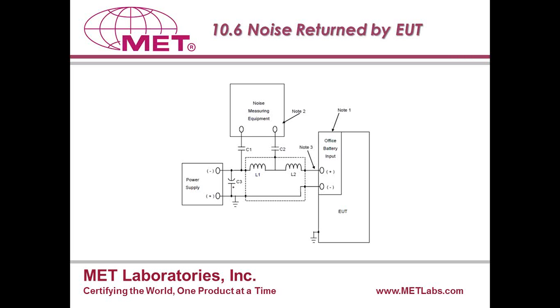safe. However, if you go back to the time when Section 10 requirements were not there and testing was being covered, especially for AT&T, by the AT&T checklist, a large number of labs were using the low frequency audio spectrum analyzer with very high input impedance, which will range up to 800 kilohms to 1 megaohm. Ideally, people were using the spectrum analyzer with 1 megaohm input instead of the 50 ohm input, which we see on a large number of these spectrum analyzers being used in the industry today.